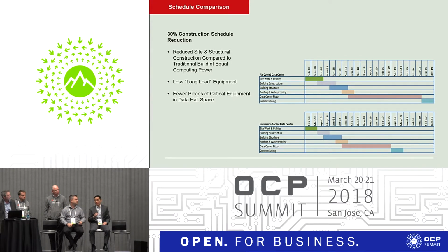Can I add something? Yes. I'd like to add another very important point. We briefly mentioned it before in the presentation, that real estate costs might also be a very important factor. With immersion cooling, we are able to increase the density tremendously, like having, for example, instead of 10 kilowatts per rack or 20 kilowatts per rack, we get 150 kilowatts per rack. So if you take a look at setting up a data center not somewhere in the Midwest, but for example in metropolitan cities closer to the New York area, or San Francisco, or overseas in Singapore, Tokyo, Hong Kong, the real estate costs over there are very, very high. So with immersion cooling, you're not only able to save money on construction cost itself, but also on the real estate cost.